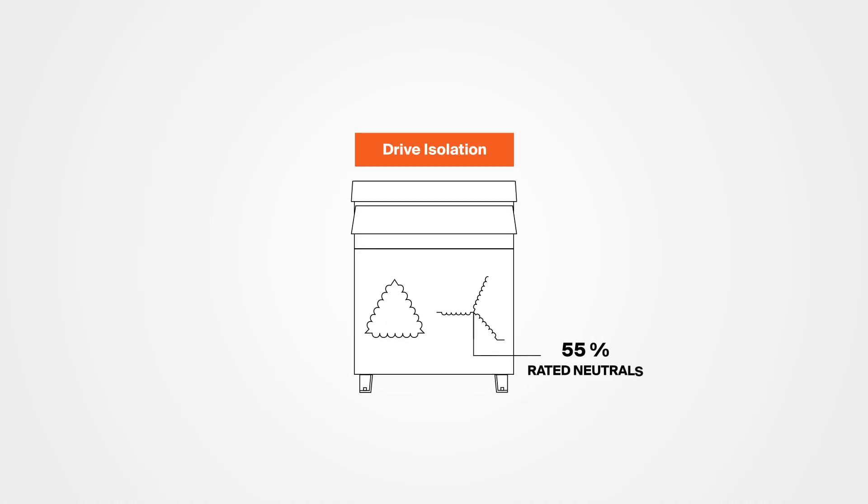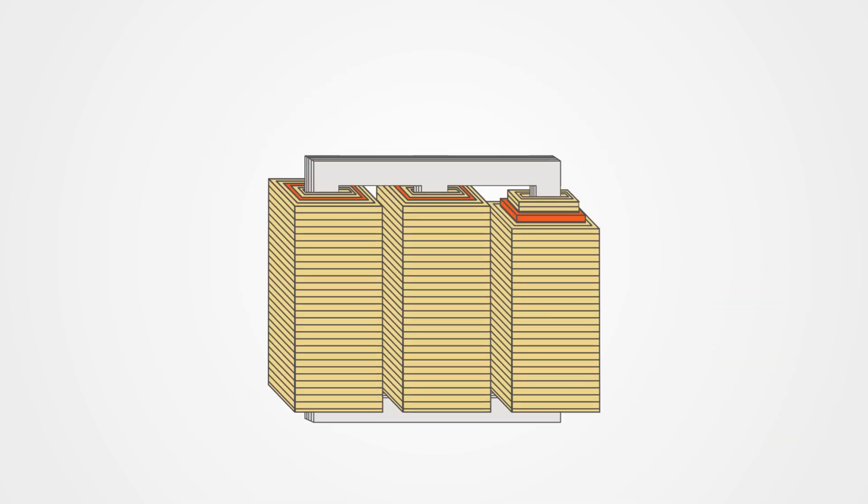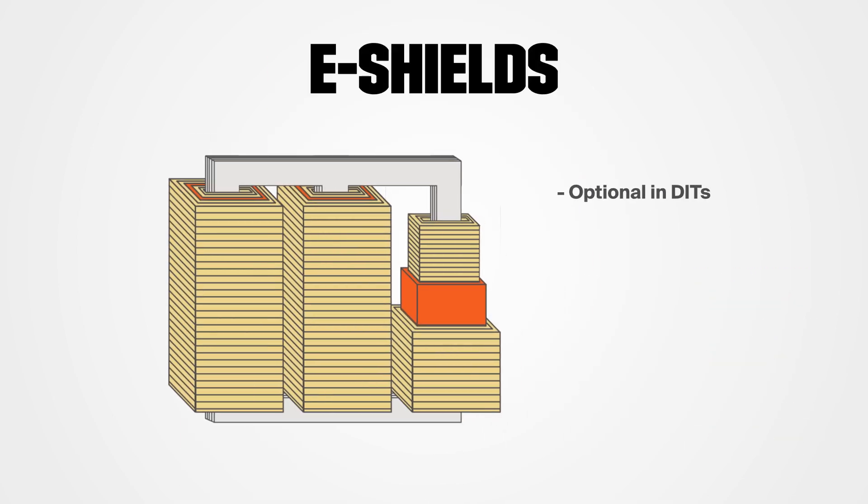Lastly, let's clear one thing up: a drive isolation transformer is not the same thing as a K-rated transformer. DITs have a 100% rated neutral, while K-rated units have a 200% rated neutral to handle triplen harmonics. Also, e-shields are optional on drive isolation units but standard in any K-rated unit. We'll cover K-rated transformers in depth in a future video, but suffice it to say they're related, but not really the same thing.